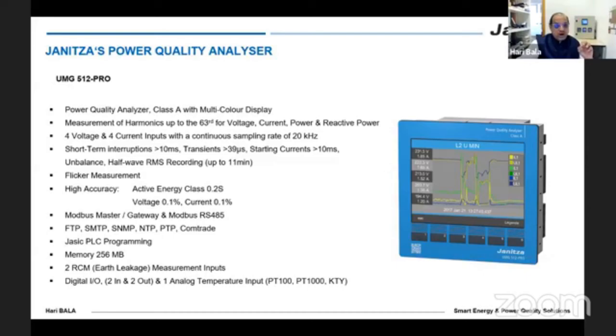We have a product called UMG 512 Pro, which is a Class A Edition 3 approved certified meter by NMI Laboratories from Netherlands. It can measure 10 milliseconds, 39 microsecond transients, which means roughly we have around 512 samples per cycle on a 50 Hertz network. We can do flicker measurements. It has an accuracy of 0.2 S class.